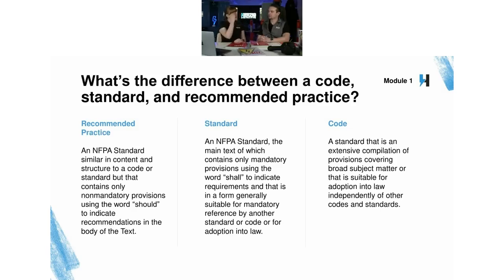And something I've noticed, Caitlyn, too, in recommended practices is outlining procedures and practices that you should follow that aren't necessarily mandatory. Yeah, and I've found that they're more thorough in the recommended practice, but once you get to the standard, you have to end up following rules, so it's less thorough. So something that's happened in the 70B, going from a recommended practice to a standard for electrical equipment maintenance, is that a lot of those practices I found to be very beneficial have actually been stripped out in the new standard.